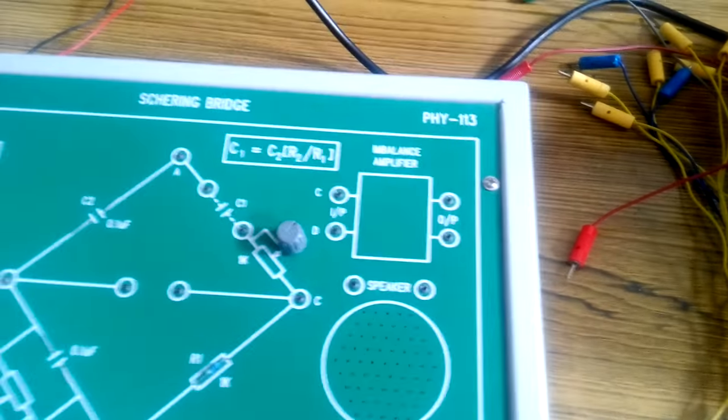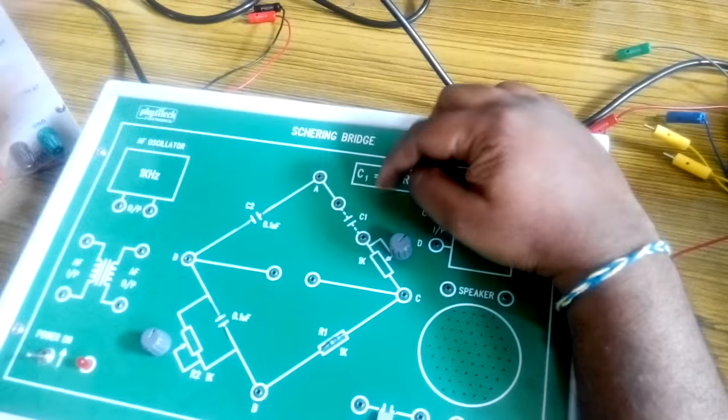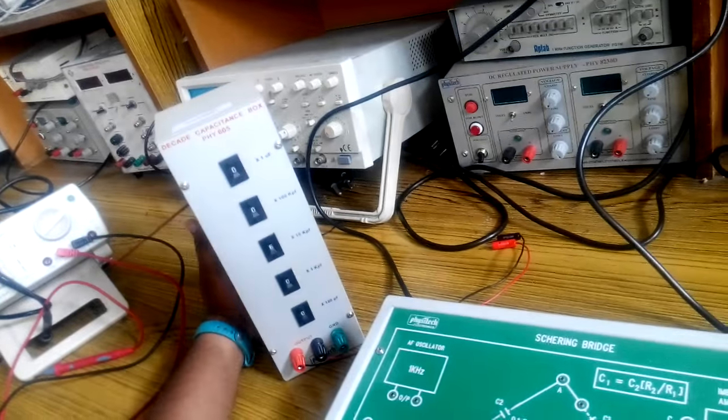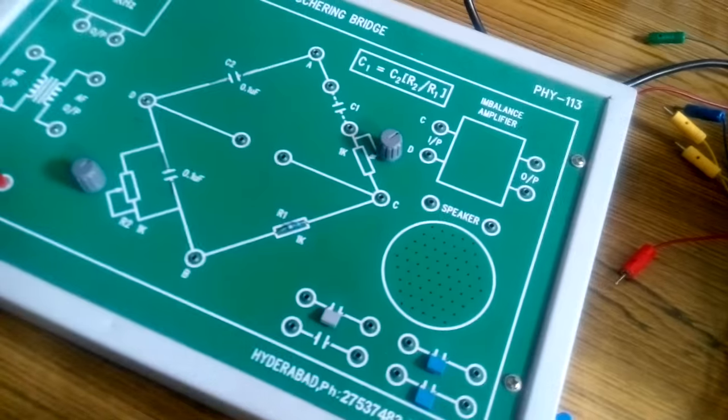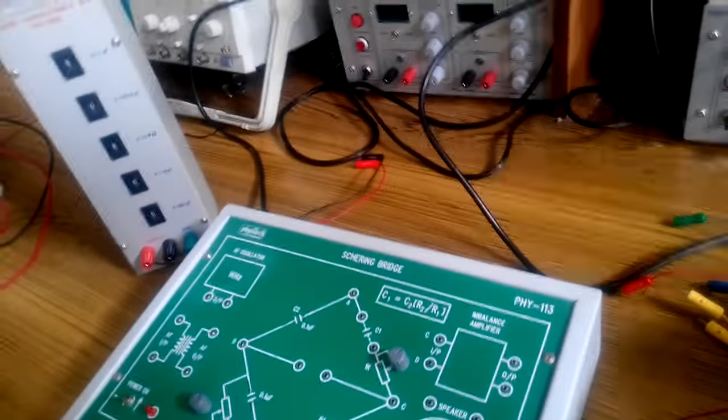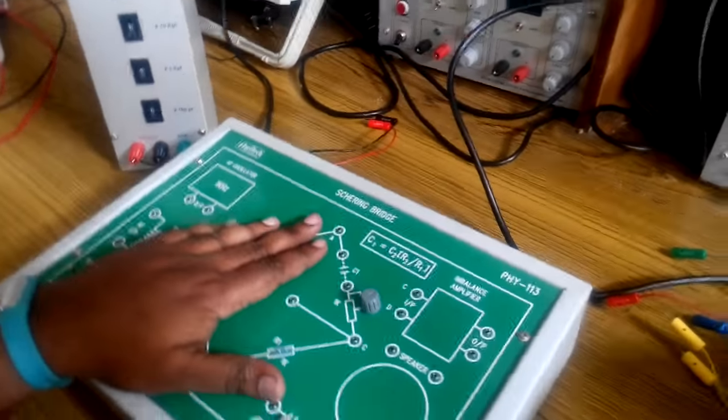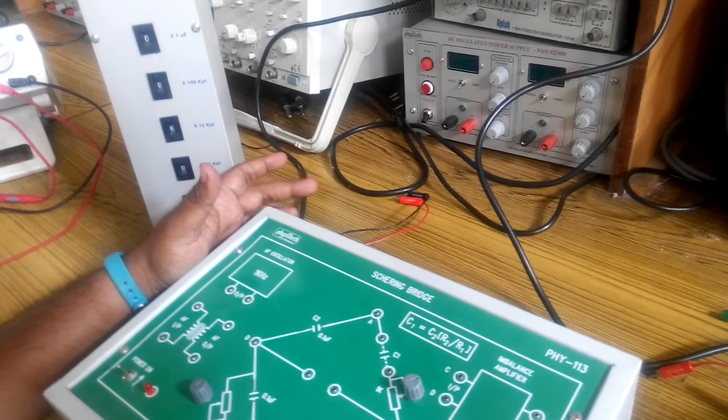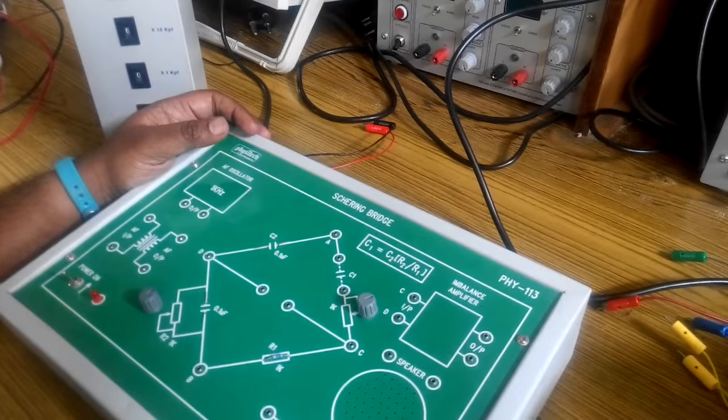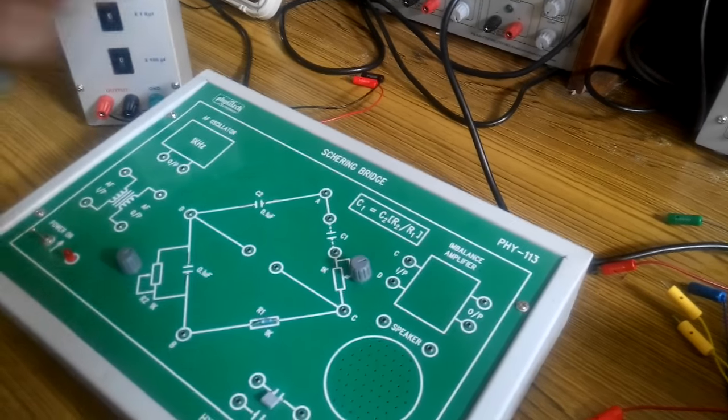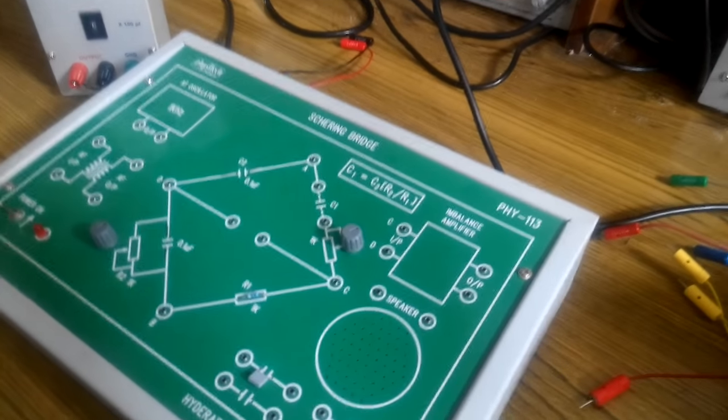It can be kept in any position except the minimum and maximum. In place of C1 over here you will be connecting a decade capacitance box, or you can even connect the capacitances that are present over here. With the help of the Schering bridge that is present over here you can measure the capacitance of the range of 0 to 100 nanofarad.